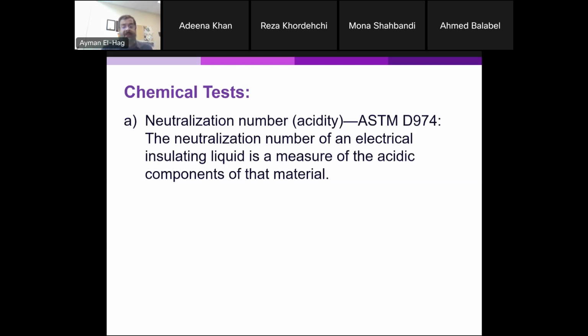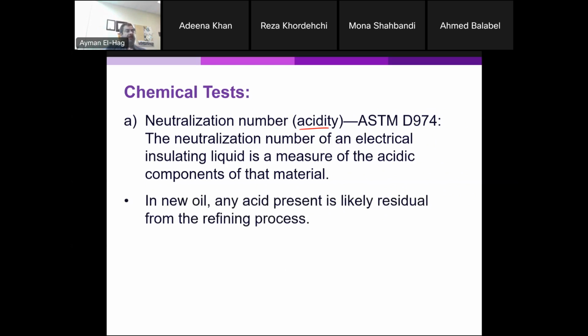Okay. Chemical test. So we have physical, we have electrical, and now we have chemical tests. Neutralization number, or sometimes we call it the acidity. It's done as per the ASTM standard D974. Now, this measures the acid number. For the acid number, the higher it is, the worse the condition of the transformer oil. So we want this number to be as small as possible. Now, if we measure some acidity in a new transformer oil that is not yet aged, this is most of the time just residual coming from the refinery process. So it's not something to worry about.